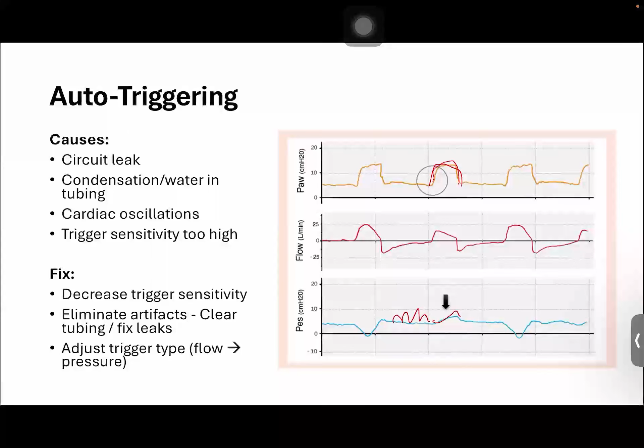So to fix that, one thing is we have to decrease the sensitivity, at least 3 to 5 liters per minute flow sensor flow trigger, and we should eliminate the artifact, water in the tubes and air leaks, as well as we can change the trigger type, flow to pressure, because then the patient needs a proper pressure drop rather than pressure flow turbulence. The patient needs a proper pressure drop to initiate the breath. So that is auto triggering.